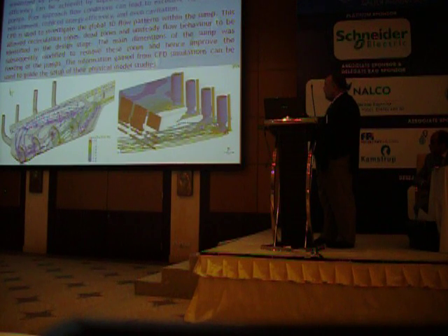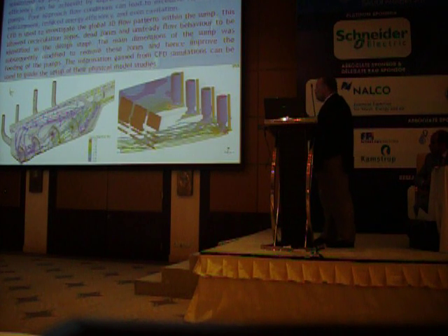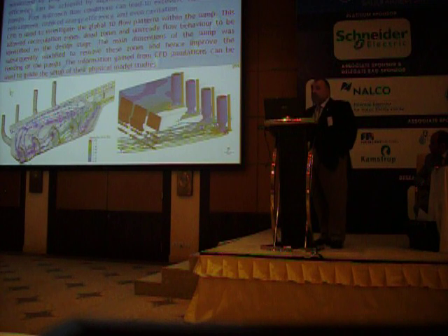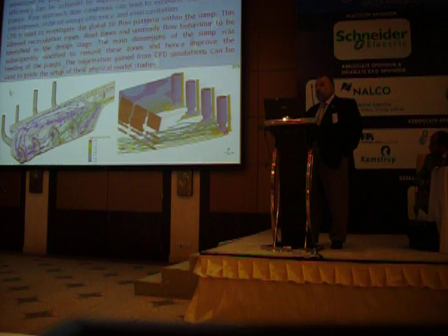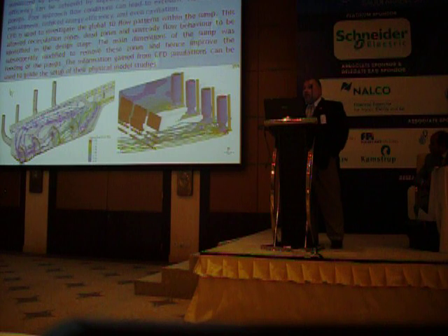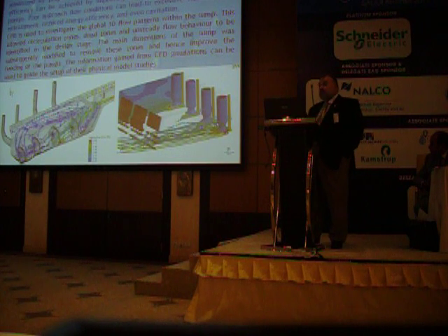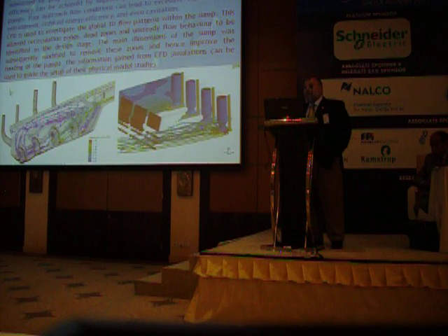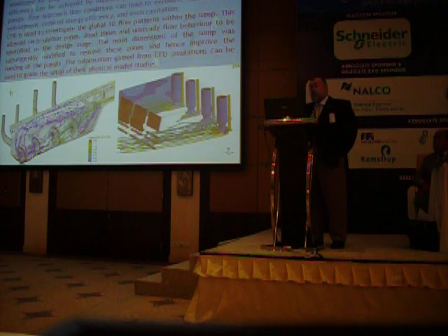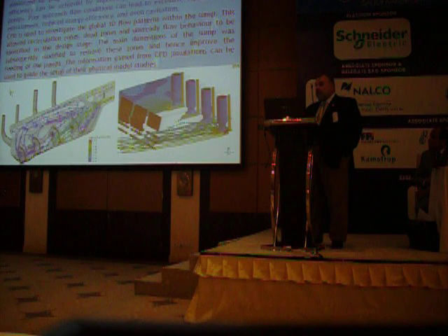And this will give you the real dimensions of the intake or of the bay or the inlet channel for raw sewage or water intake in desalination plants, because most of us just fix such dimensions and ensure the capacity of the wet well according to the stop and start of the pump and the volume added, and then you will say, okay, I need this volume as per motor cycles on and off per hour like this, and then you will give a very big wet well capacity, and the civil work will be highly costly and also other subsidiary costs. Thank you.